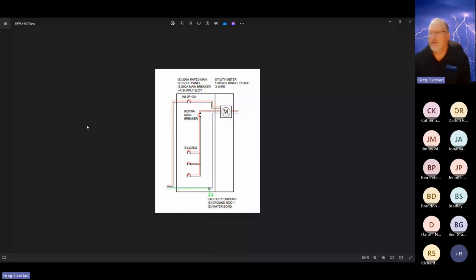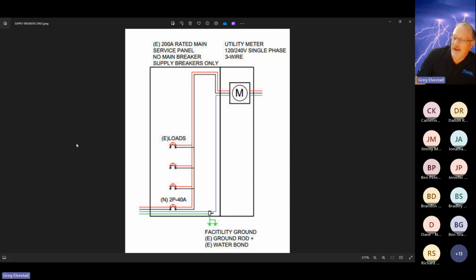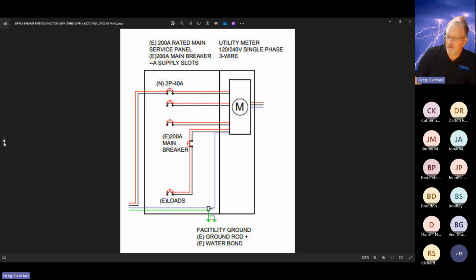First one on the screen, you may have seen this one. 400 amp service panel with 2 slots, one not being used, one being used. Use a supply breaker. That's an option. And this one is just like that panel that I showed you earlier, with no breaker, turning off the bus bar, and capability of having 4 circuits on it. Solar connection right there. Very simple. Again, supply side. And another version with multiple ones. There are different panels out there.